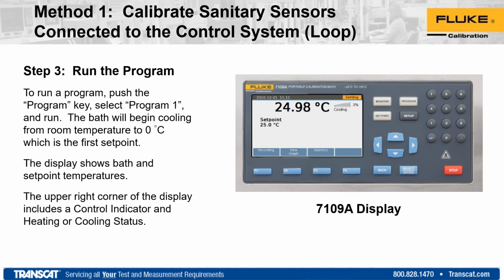So I didn't go through the ins and outs of setting up the entire process, but we're going to assume that we've already got that pre-programmed. We're going to select our program 1 key, which is the pre-selected program that we've determined to run to those 3 points, and we're going to tell it to go. Once that's enabled, you're going to see the bath come up and kick on. You're going to see the cooling power come up, and the bath will start to cool to that first set point of 0. You can also watch the bath as it's coming down to temp.